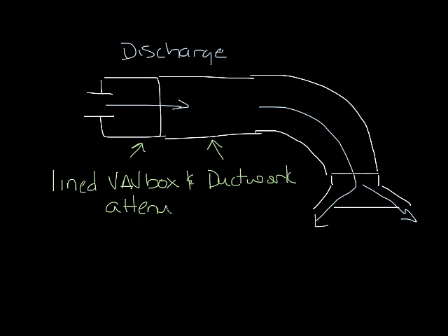And diffusers usually have flex duct, which is also an excellent attenuator of VAV box sound coming down the ductwork. It can reduce the mid-frequencies by 20 dB or more. For this reason, discharge sound of VAV boxes is not usually a big concern. We do see a lot of unlined ductwork. If you have unlined ductwork, you need to be careful about discharge sound.